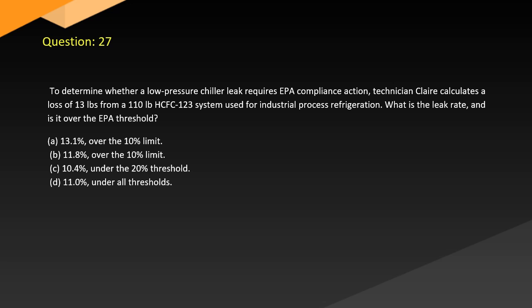Question 27. To determine whether a low-pressure chiller leak requires EPA compliance action, technician Claire calculates a loss of 13 pounds from a 110-pound HCFC-123 system used for industrial process refrigeration. What is the leak rate, and is it over the EPA threshold? A. 13.1%, over the 10% limit. B. 11.8%, over the 10% limit. C. 10.4%, under the 20% threshold. D. 11.0%, under all thresholds.